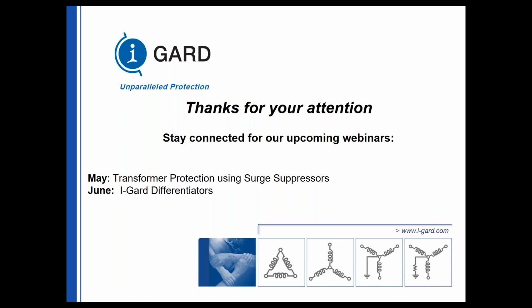Excellent. The next one is, we have a 15 kV application where such a tester would be handy. Can it be made compatible with third-party voltage sensors, no VTs, to expand the voltage range to 15 kV? I've been asked that question many times, and I've been thinking about how to implement an absence of voltage tester on a 15 kV system, or 5, anything greater than 600 volts. But part of 1436 means we have to test phase to phase and phase to ground to establish an electrical safe work condition. I'm not sure right now how I can do that with present technology. We haven't stopped thinking about it, and we have been asked several times on how to do this.